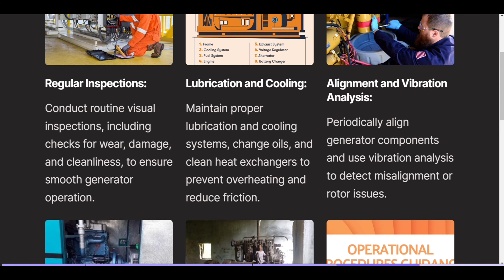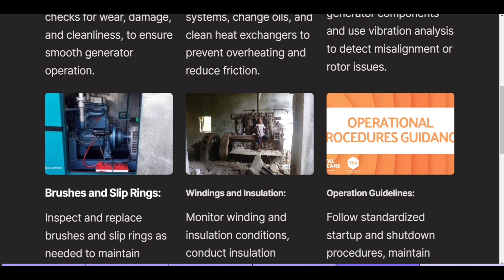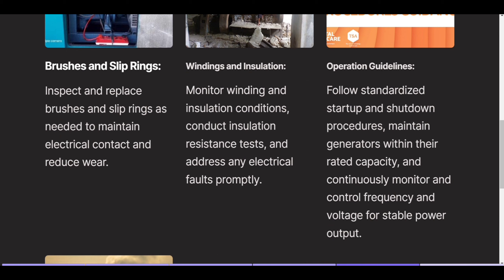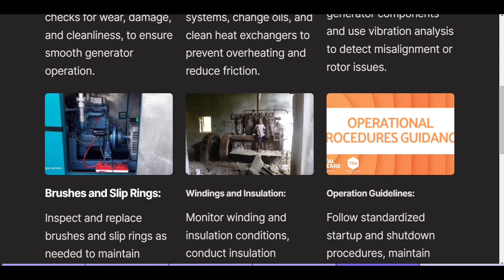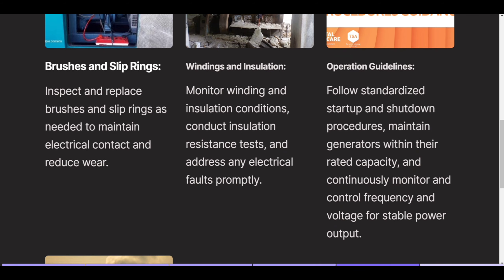Alignment and vibration analysis: periodically align generator components and use vibration analysis to detect misalignment or rotor issues. Brushes and slip rings: inspect and replace brushes and slip rings as needed to maintain electrical contact and reduce wear. Windings and insulation: monitor winding and insulation conditions, conduct insulation resistance tests, and address any electrical faults promptly.